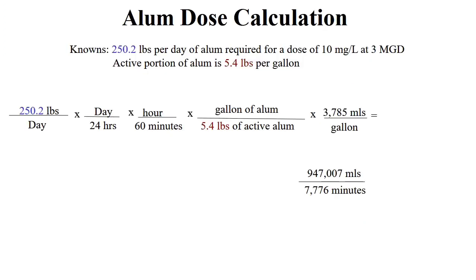We multiply 0.49 times 11 to determine that there are 5.4 pounds of aluminum sulfate in a gallon of alum. For any chemical, once we know the pounds per day we need to feed and the pounds per gallon of the active ingredient in our chemical, we can determine the accurate feed rate. We know we want to feed 250 pounds per day, and alum has 5.4 pounds per gallon.